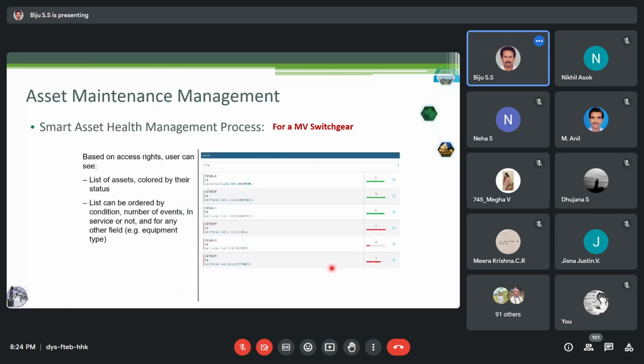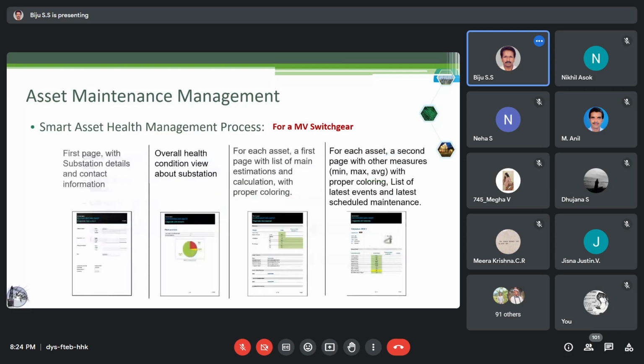Again, you have dashboards listing out all the statuses of various equipment on a single platform. These are different shots of the dashboard. You have equipment information here and overall health condition here. Then it will give the main estimations and calculations, like the maximum and minimum, the maximum life of this equipment, and the maximum load it has carried. Then again, we use the minimum, maximum, and average values with proper color coding. A list of the latest events, switching operations, fault interruptions, and everything will be given here. And the last scheduled maintenance, when it was carried out, will be listed here.